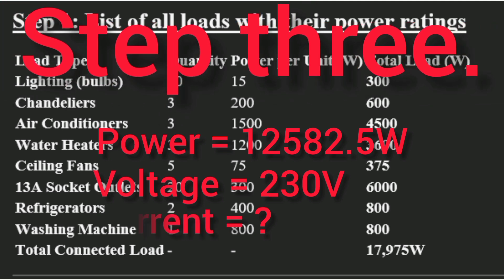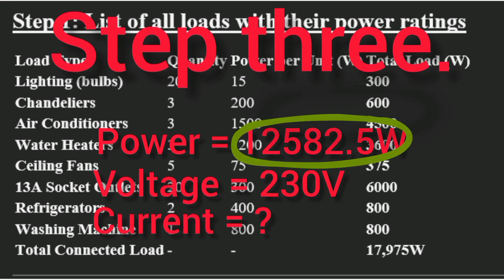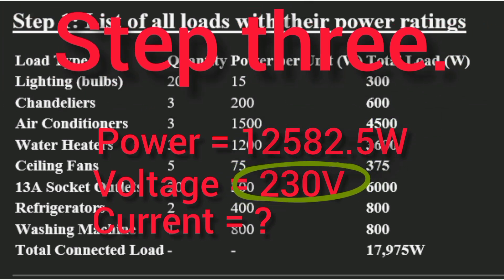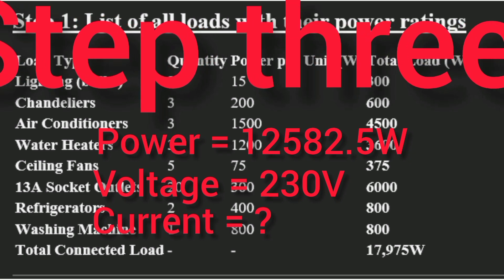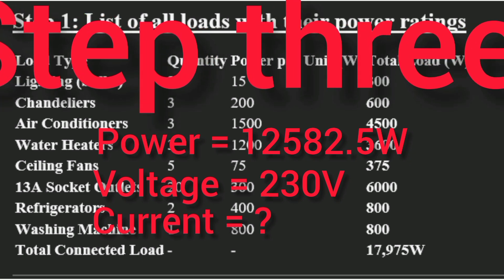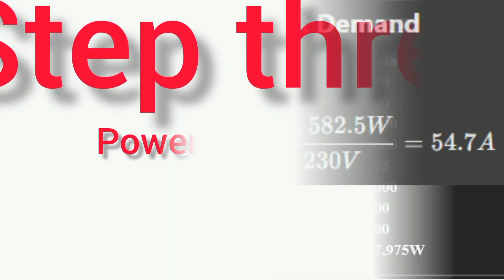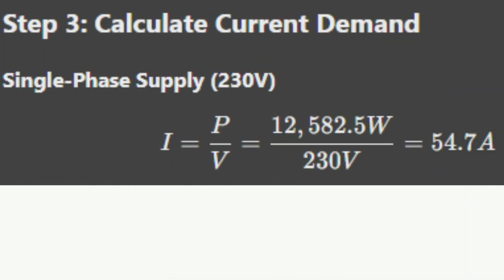To get the demand current we divide the demand power by the voltage. In some cases we also multiply the voltage by power factor, but we will address that later. So demand current = 12,582.5 watts ÷ 230 volts = 54.7 amps. If we find a cable that can safely carry 54.7 amps, we can use it as our service cable.